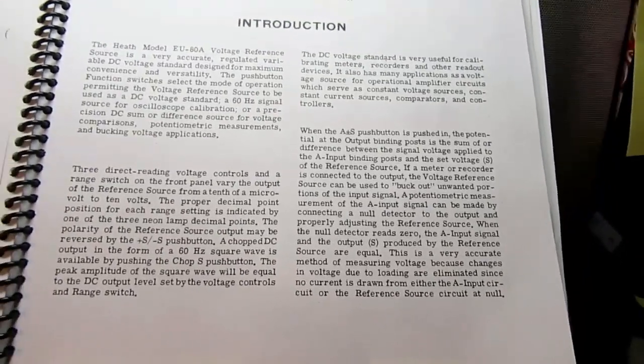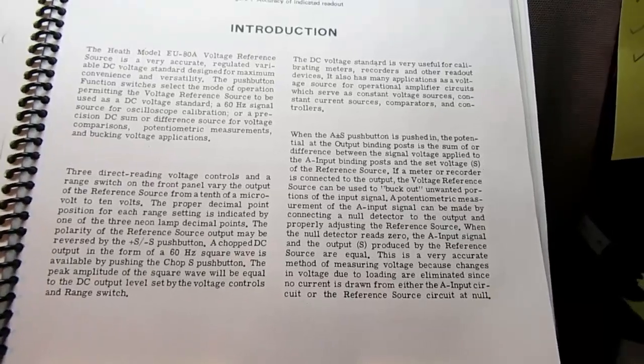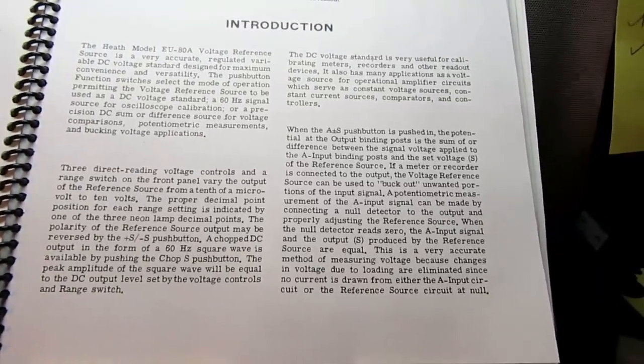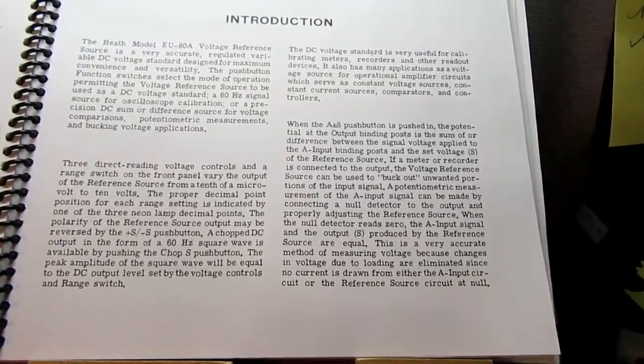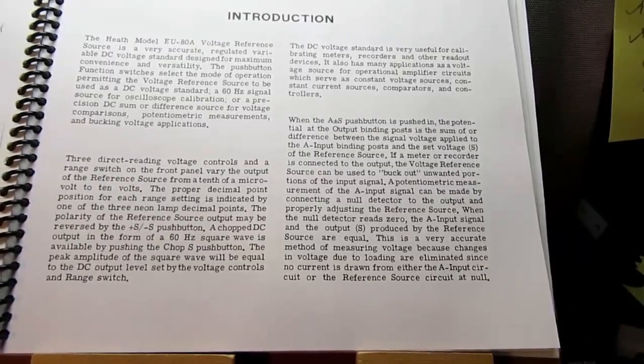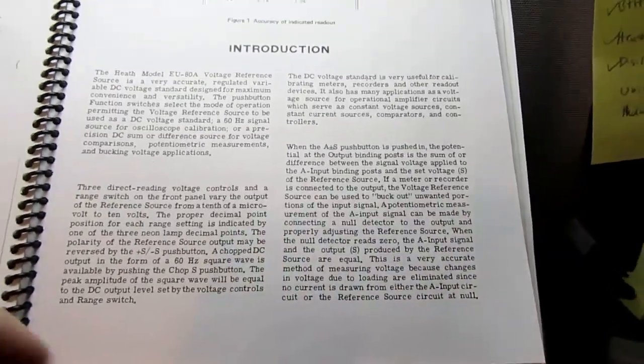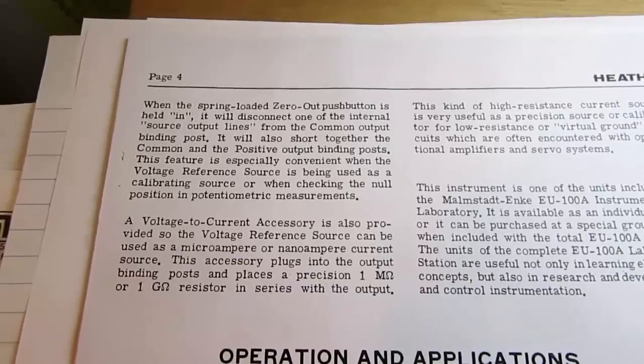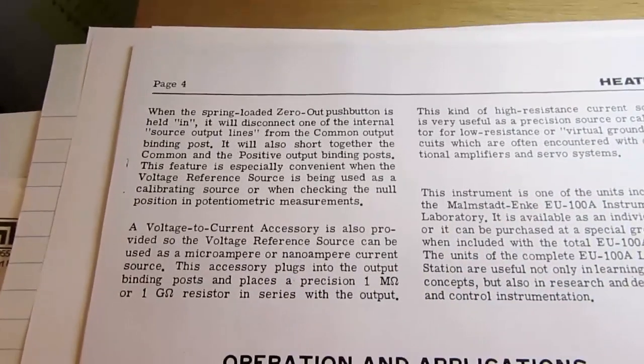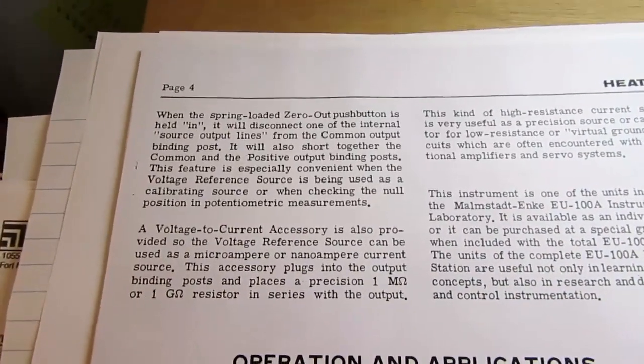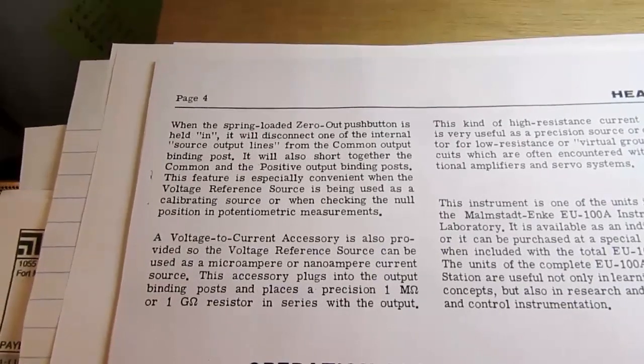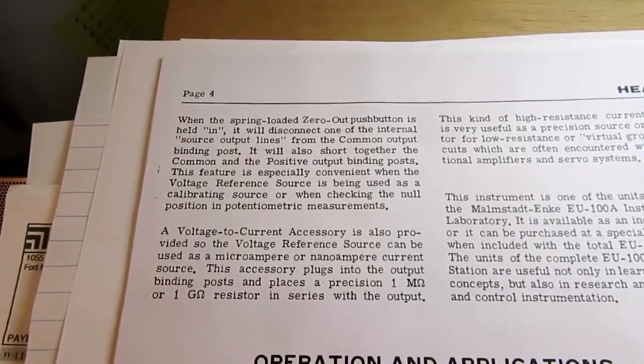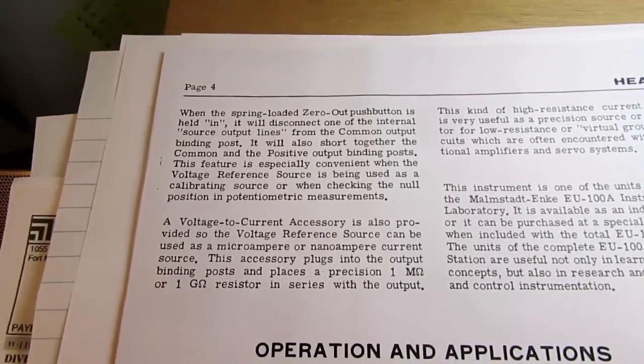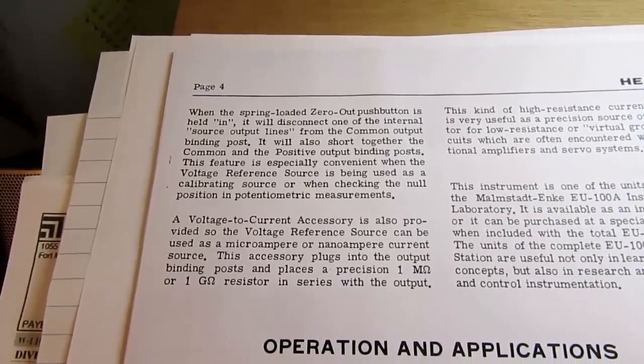This is a very accurate method of measuring voltage because changes in voltage due to loading are eliminated, since no current is drawn from either the A input circuit or the reference circuit at null. With the spring-loaded Zero-Out push button, when that is held in, it will disconnect one of the internal source output lines from the common output binding post. It will also short together the common and the positive output binding posts.